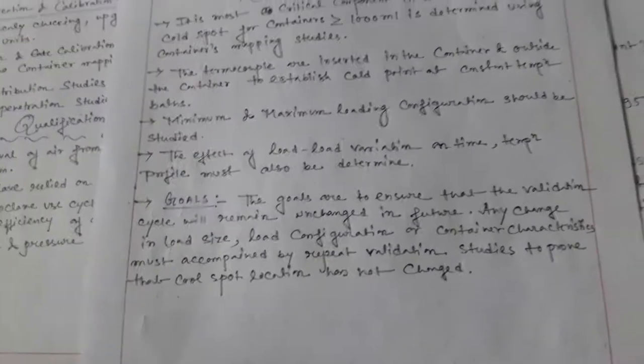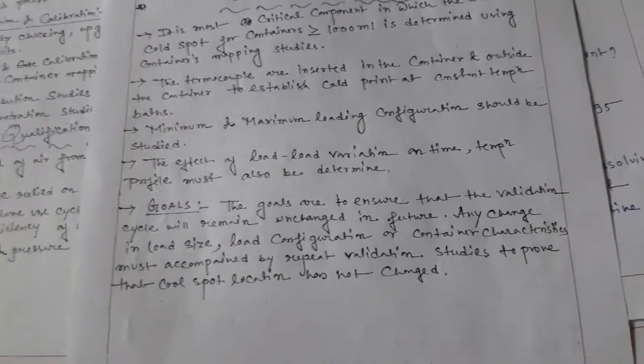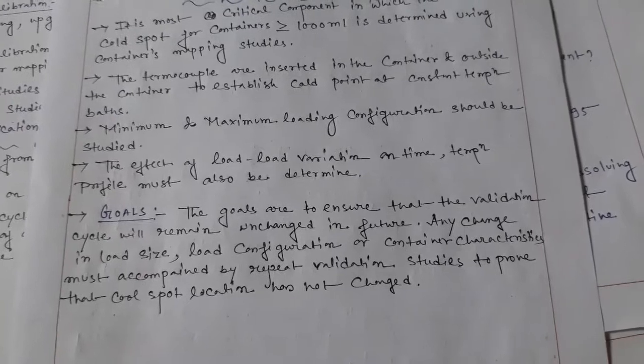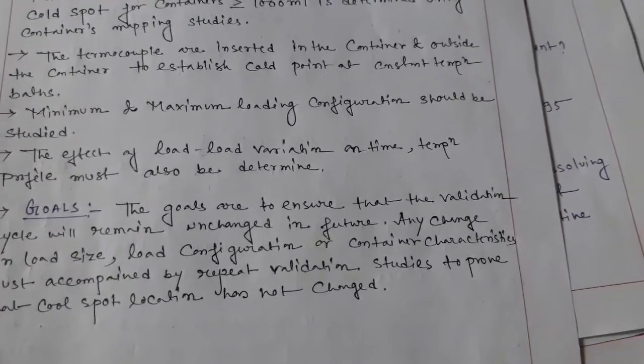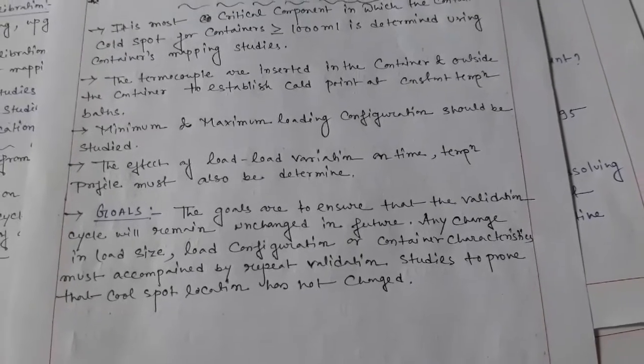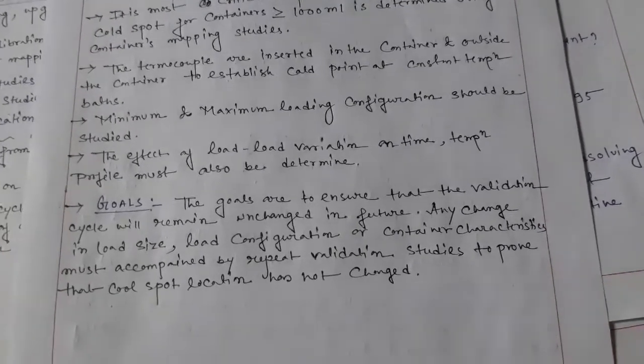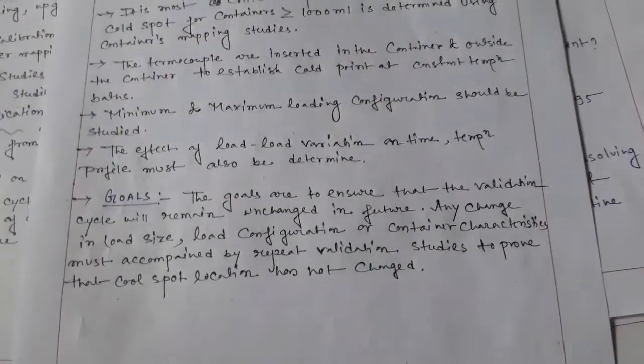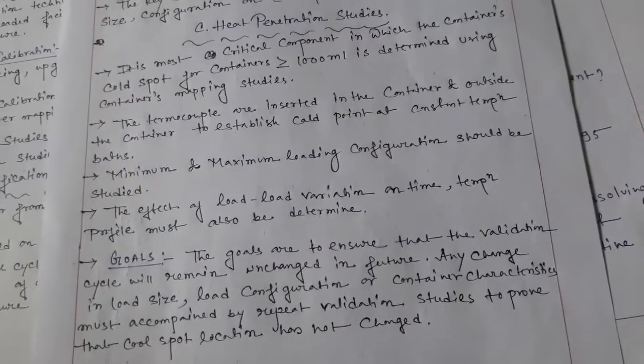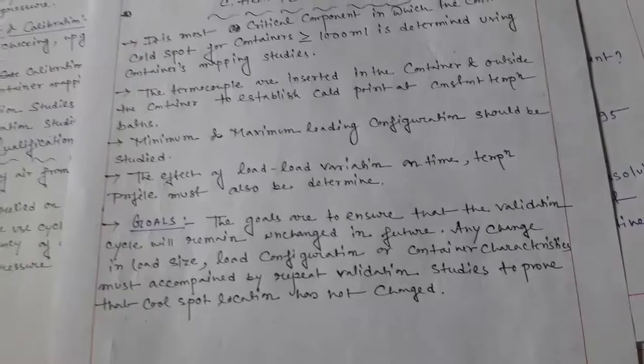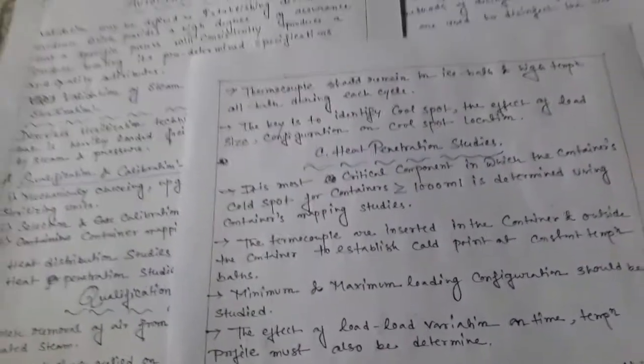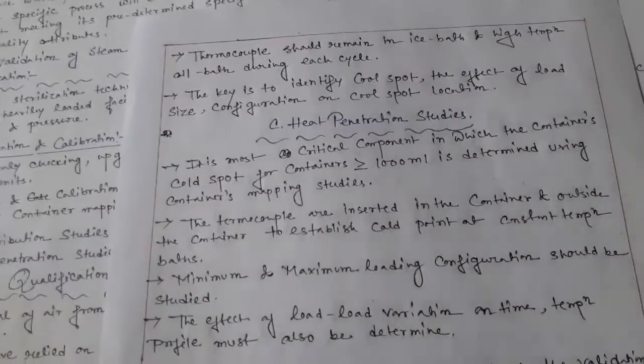The goals are to ensure that the validation cycle will remain unchanged in the future. Any change in load size, load configuration, or container characteristics must be accompanied by repeat validation studies to prove that the cool spot location has not changed. These points are very important for moist heat sterilization and autoclave validation.